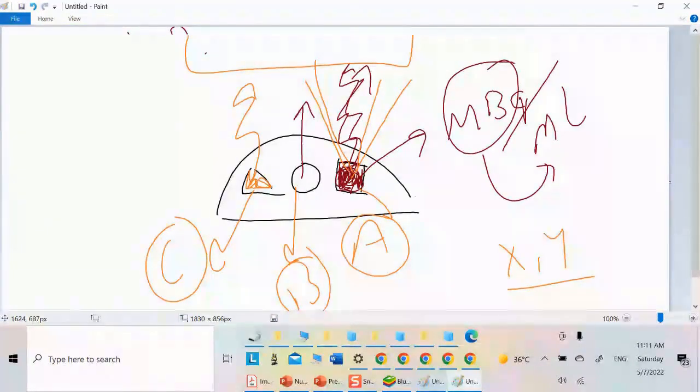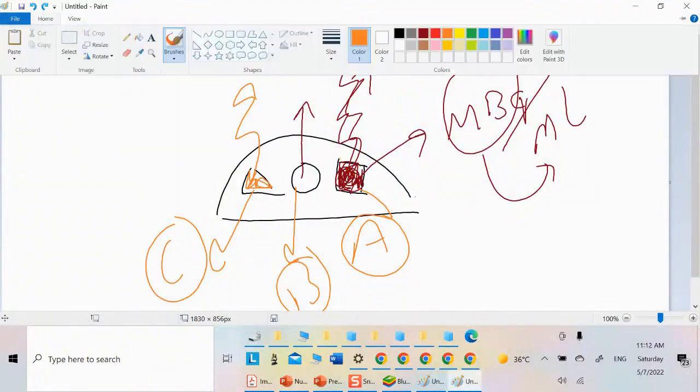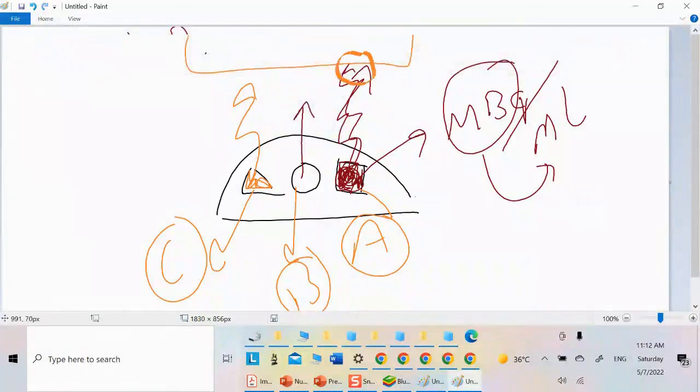So what will you benefit from this? I will benefit that the photon coming in perpendicularly to the hole will interact at a specific point on the crystal. When this interaction occurs at that particular point on the crystal, it leads to excitation and releases an electron. The structure of the crystal, as we discussed in previous lectures, includes something called the valence band and the conduction band. The scintillation occurs, and the electron moves to the conduction band and then drops back to the valence band, emitting light. The emitted light can be, for example, around 5,000.